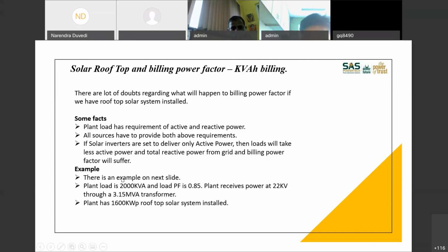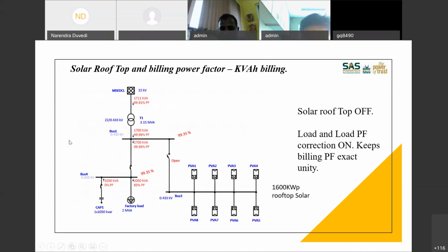I have taken an example. Plant load, let's say, is 2000 kVA, and the load power factor is 0.85. Plant receives power at 22 kV through a 3.15 MVA transformer, and the plant has a 1600 kWp rooftop solar system installed. This is the system which I am referring to. There is a 22 kV grid. You have a 3.15 MVA transformer. There is a bus on which you have a 2 MVA plant load, which has 85% power factor.